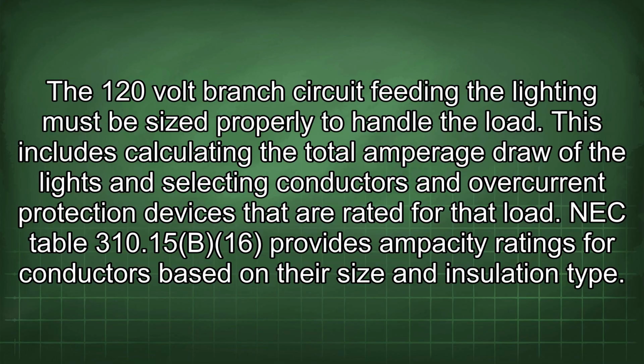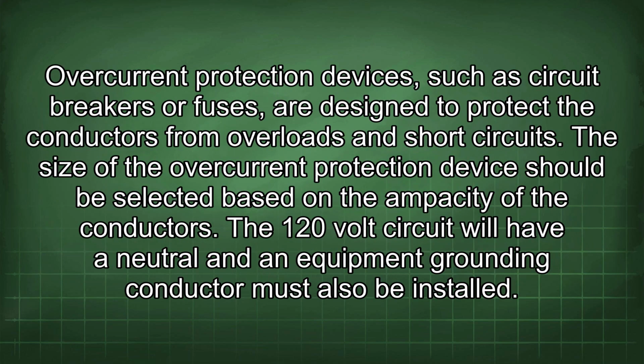This includes calculating the total amperage draw of the lights and selecting conductors and overcurrent protection devices that are rated for that load. NEC Table 310.15(B)(16) provides ampacity ratings for conductors based on their size and insulation type. Overcurrent protection devices, such as circuit breakers or fuses, are designed to protect the conductors from overloads and short circuits. The size of the overcurrent protection device should be selected based on the ampacity of the conductors.